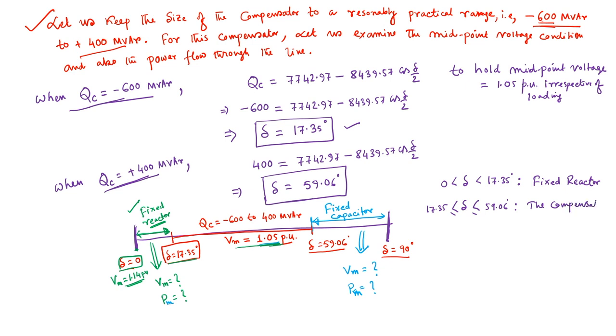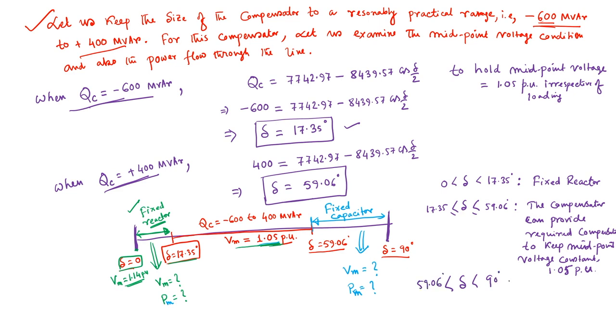the compensator can provide the required compensation to keep the midpoint voltage constant, that is 1.05 per unit. And when delta varies between 59.06 degrees and 90 degrees, then it will act as a fixed capacitor mode.